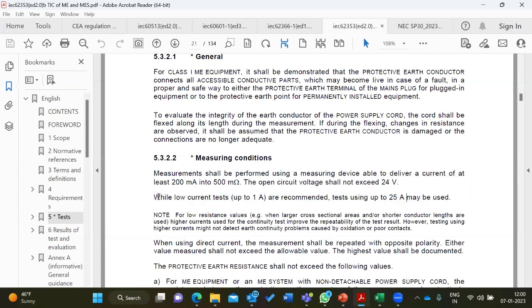See, if you look at a continuity resistance meter of 1 ampere or 25 ampere, these are not small multimeters. These are called high current micro-ohmmeters. Micro-ohmmeter means it can measure very, very low resistance connections.